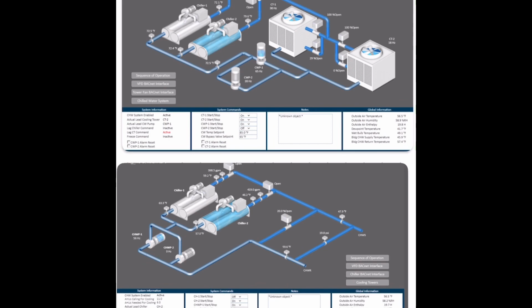Alright, so last but not least, we're gonna talk about the condenser side of the system. I put cooling side as well. It's right here, which we already talked about and we already look at it. And now we're gonna look into the condenser side of the chiller system and cooling towers, which is over here in the top of the picture. So you can get an idea of how the water cycle works on your chillers on the condenser side. The only difference between these chillers, centrifugal and cooling towers, from the air condensing chillers is that instead of using condenser motors and air to subcool our refrigerant, we use water and the cooling tower that's gonna help us with the subcooling on the condenser side.